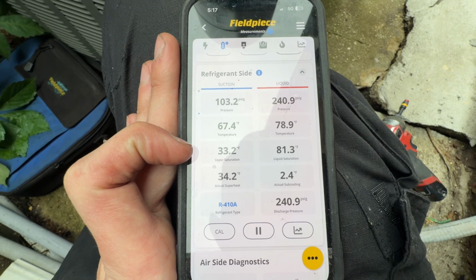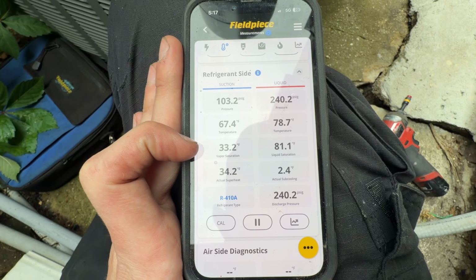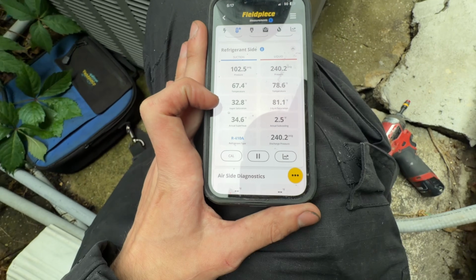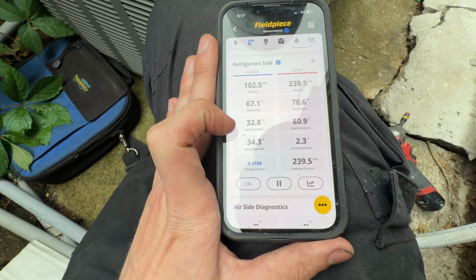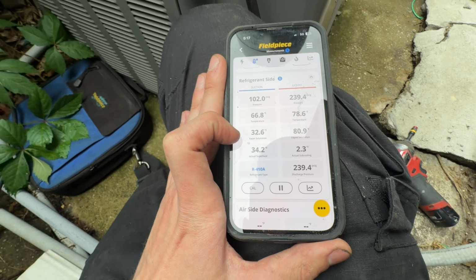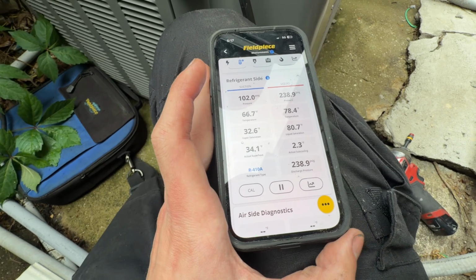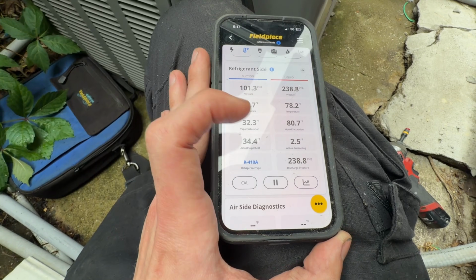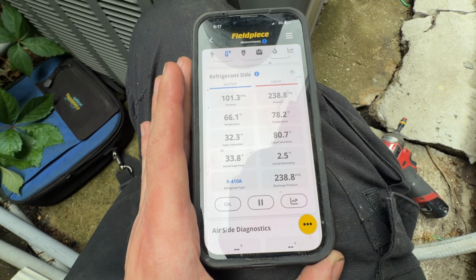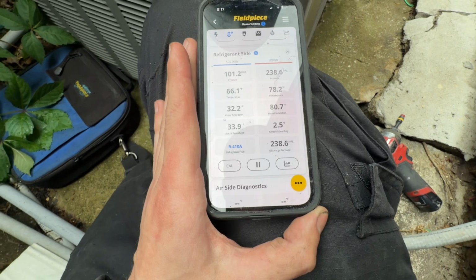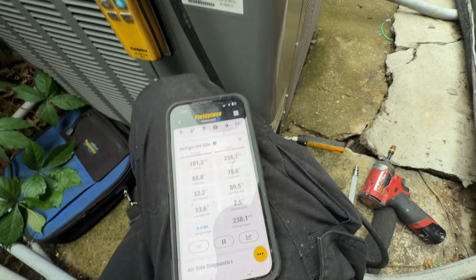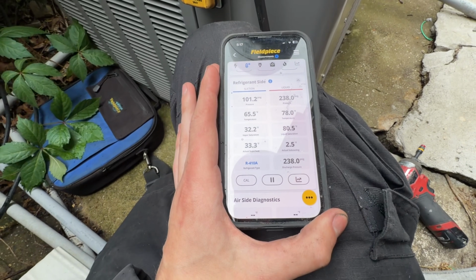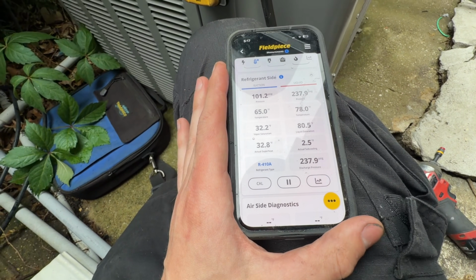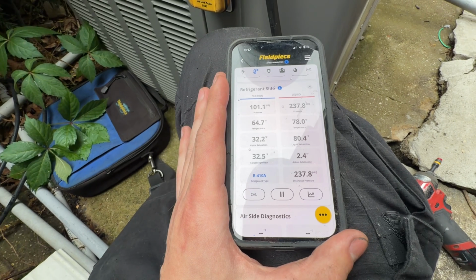See, our vapor saturation is holding a little bit higher than it was before. Usually around 40, 43 degrees is where that tends to be, but it changes. Subcooling is starting to get a little bit higher. It could take up to 15 minutes for it to really stabilize, but usually it happens fairly quickly.